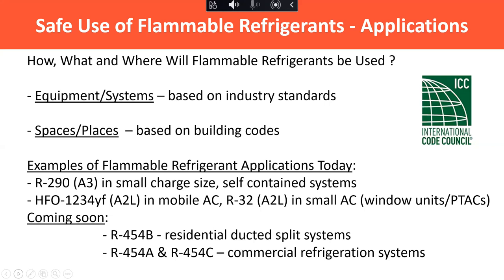Things like R454B is one of the leading A2L replacements for 410A. And then on the commercial refrigerant side, there's 454A and C. Those are kind of designed to match 404A properties, but again, very low GWP and mildly flammable. So that's where we're going to be seeing those things coming soon.